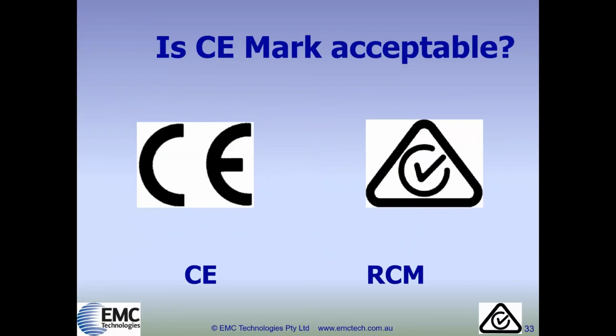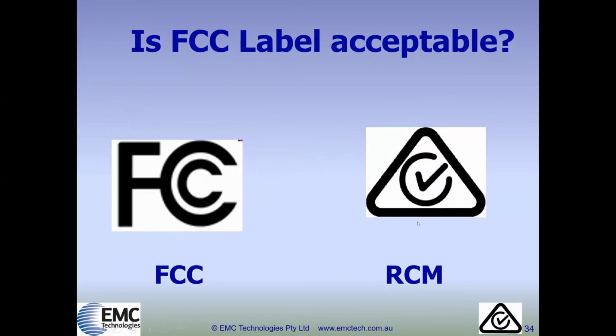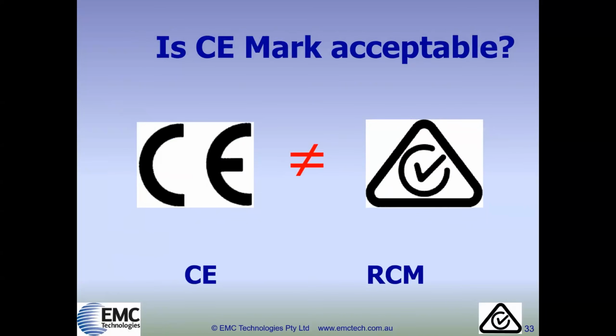Now, a common question: our product is CE marked. Is that okay? Do we have to apply the RCM label? Well, the answer is yes, because the CE mark is not recognised legally in Australia. The same with the FCC logo, it's not recognised in Australia. However, you may use the CE test report, if it was done at 220 or 230 volts, to show compliance in Australia for the RCM compliance. So you don't need to retest.